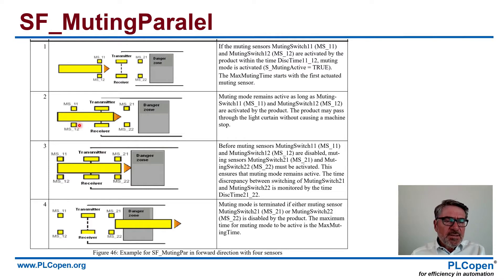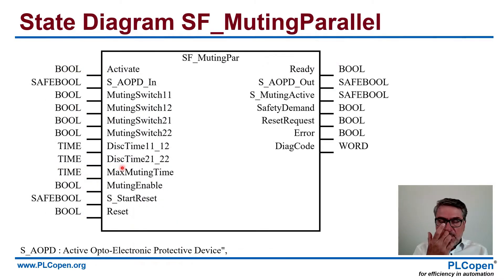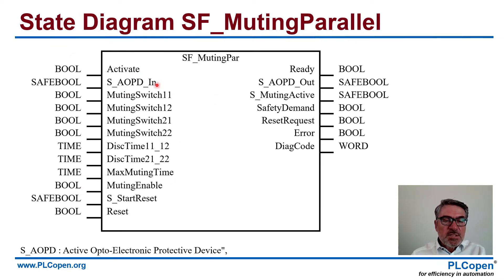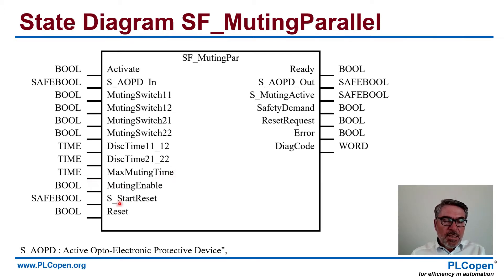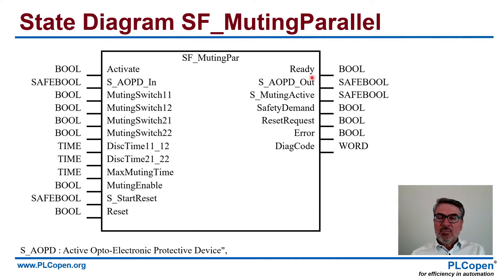In that way, it can detect it's a car body over its length and not a person walking in. This is the parallel muting function block. You see the inputs on the left and the outputs on the right. You see the muting switches — four pieces — the discrepancy times between the switching on of those, and the max muting time of the whole process. Muting enable, start, reset. The AOPD is the active optoelectronic protective device — this is what we are looking at and moving toward. And here you get the relevant outputs.